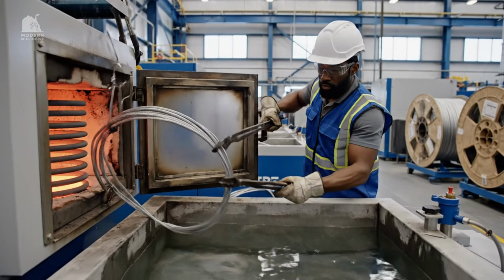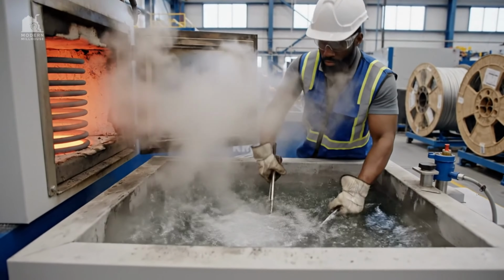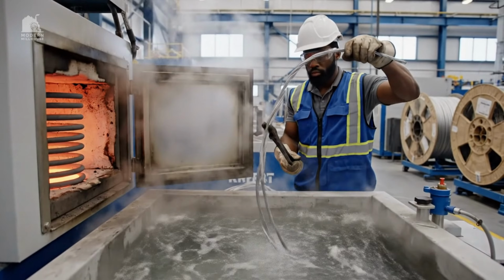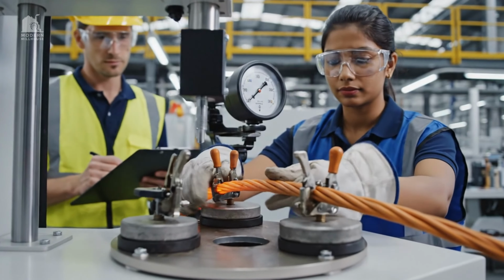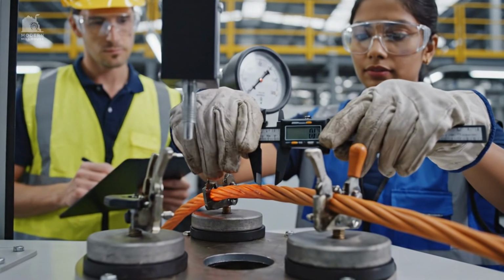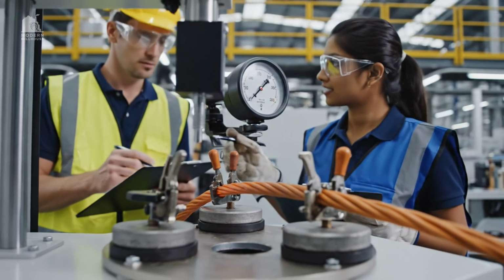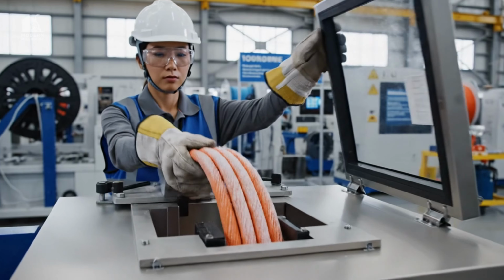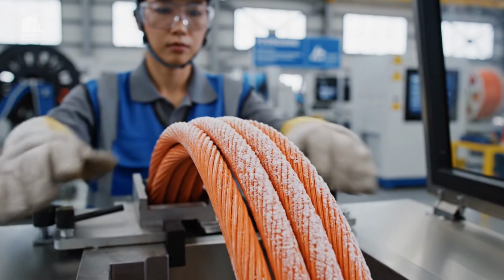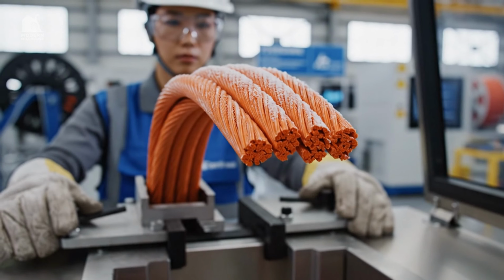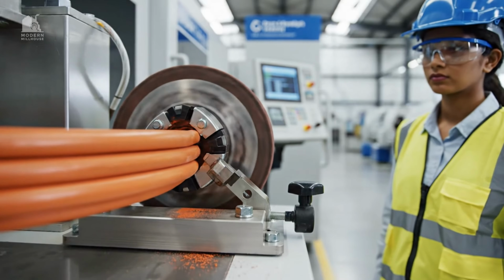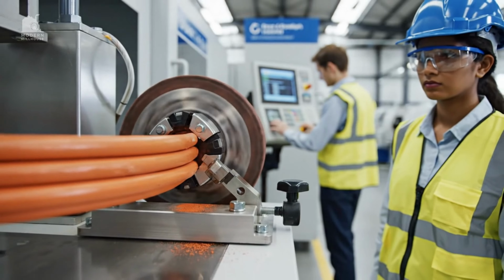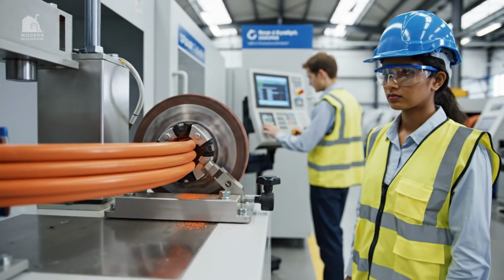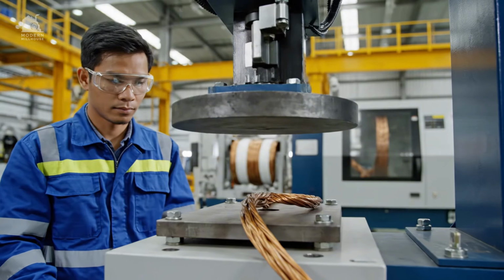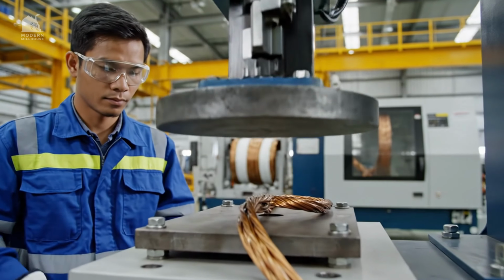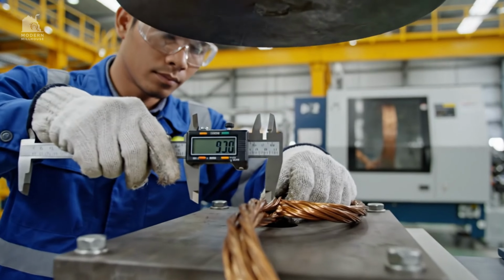Heat shock tests how insulation handles sudden temperature changes without splitting or deforming. For higher temperature compounds, hot deformation checks confirm the polymer won't creep under heat. Cold bend checks winter performance, when polymers stiffen and small flaws can turn into cracks. Abrasion testing estimates how jackets survive scraping during pulling through conduit and tight spaces. Some tests look for deformation under pressure, important for cables squeezed in tight bundles.